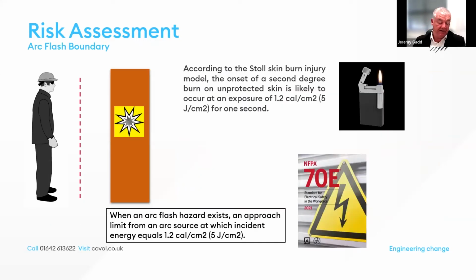In terms of boundaries, once the incident energy levels have been determined, the arc flash boundary can then be determined itself. The boundary is a distance where incident energy levels are equal to or less than 1.2 calories per centimetre squared. The basis for this energy level is from experimental results obtained by Stoll and used to determine the rate of tissue damage. You can see there the lighter with a naked flame: you put your hand over a naked flame and you're going to start to burn flesh, and that's basically what that piece of work by Stoll determined.